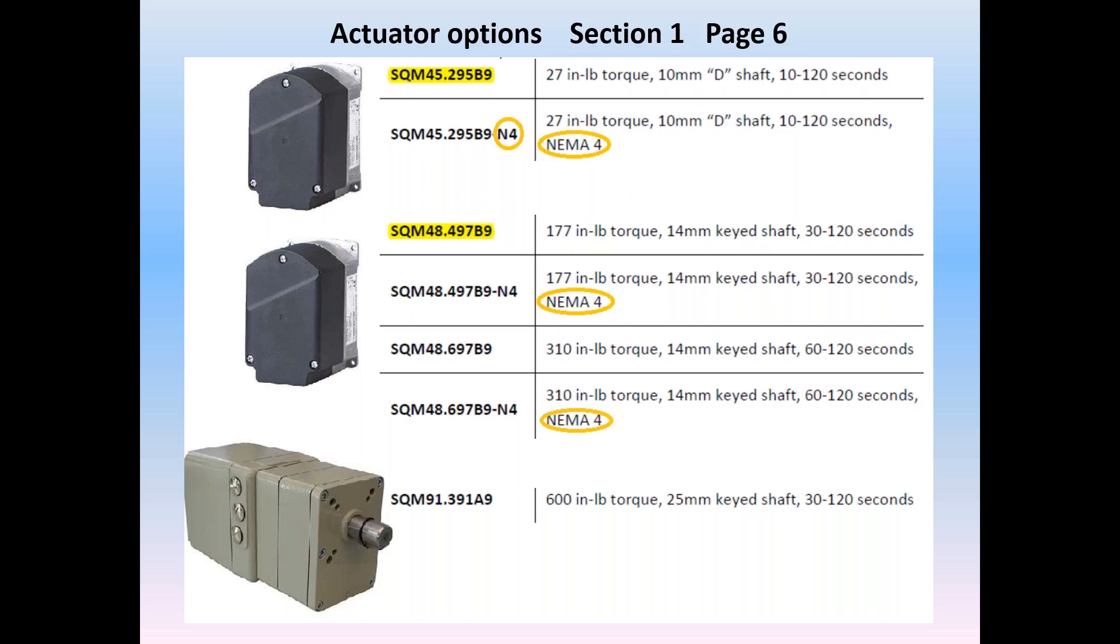All units can be addressed as needed and will follow the LMV's program for clockwise or counterclockwise rotation. These actuators feature repeatable resolution of one-tenth of a degree positioning with dual and redundant position feedback, utilizing factory calibrated hall-effect sensors for a long-life, safe, and trouble-free operation.